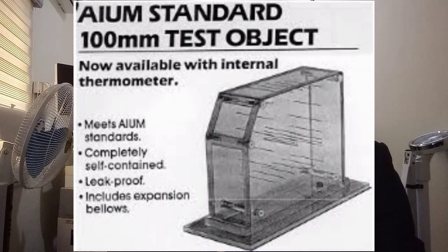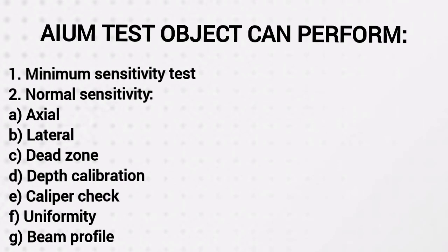Although it is designed for an A mode and static B mode image system, it has been used to test real-time ultrasound scanners. AIUM 100 mm test object can perform the following quality assurance tests. Sensitivity: it is used to test minimum sensitivity. It also performs normal sensitivity tests like axial resolution, lateral resolution, dead zone, range accuracy or depth calibration, caliper check. Uniformity testing is part of what it performs. Beam profile is also included.